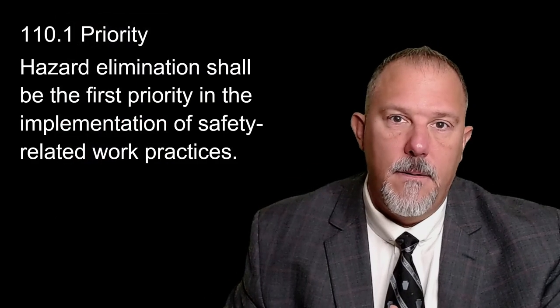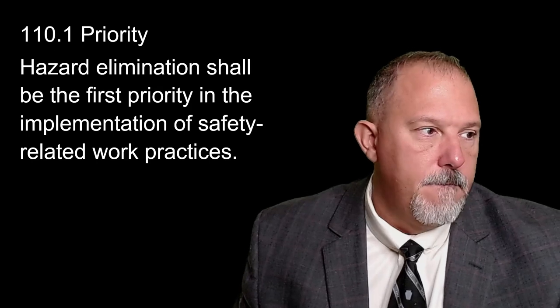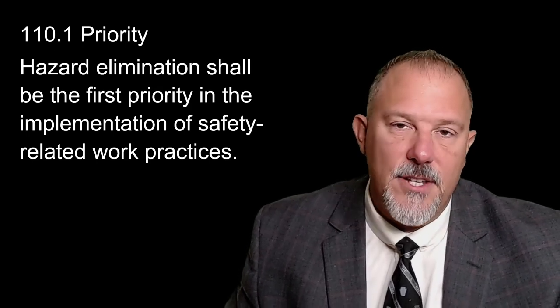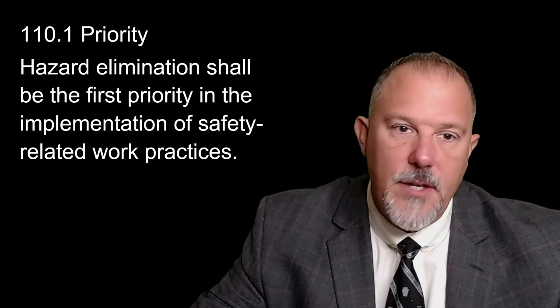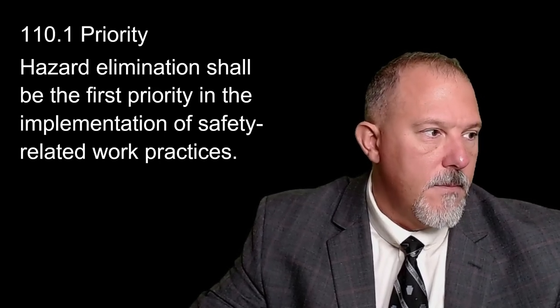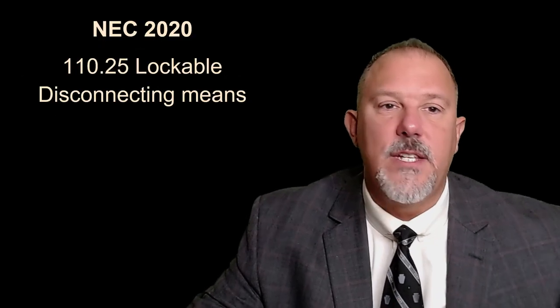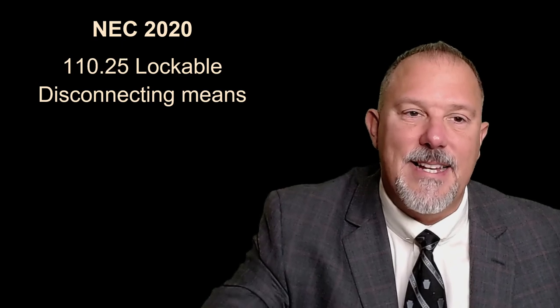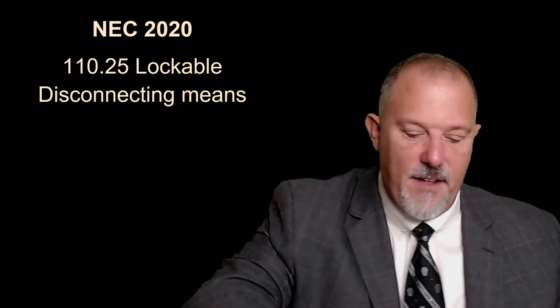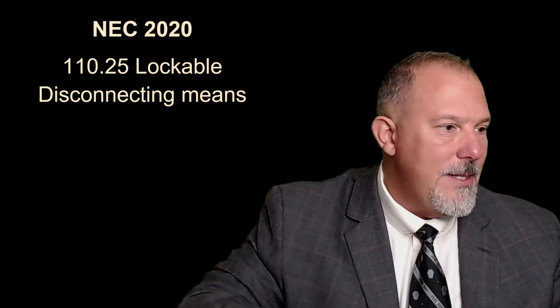We have to understand the arc flash hazard, the arc blast hazard. We have to understand the shock hazard. And we need to follow 70E safe work practices. But even more importantly, we need to leverage safety by design to meet this number one priority, hazard elimination. That has to be your number one priority. One of the best and easiest ways to do that is to provide lockable disconnecting means. NEC 110.25. Think about NEC 110.25.